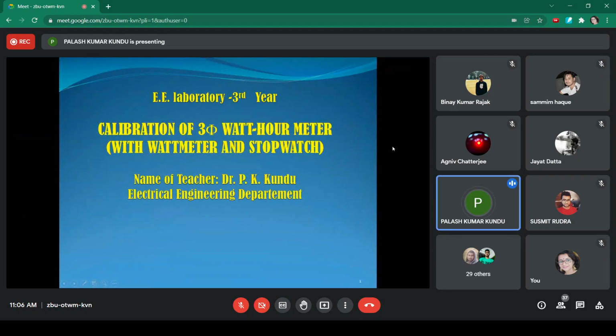I think all of you are familiar with the working principle of the induction disc type energy meter or watt-hour meter. The induction disc type energy meter for polyphase systems or three-phase systems uses a two-element induction disc type, and they have a common mechanical linkage. With the help of the registering mechanism, if we recall our basic knowledge of the working principle, according to the 2 watt-meter method, there are two elements in construction.